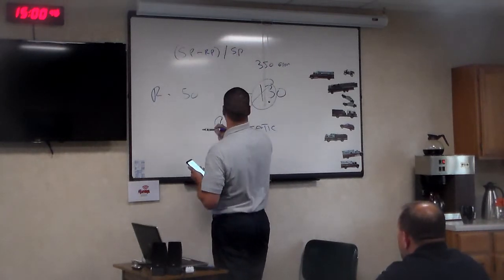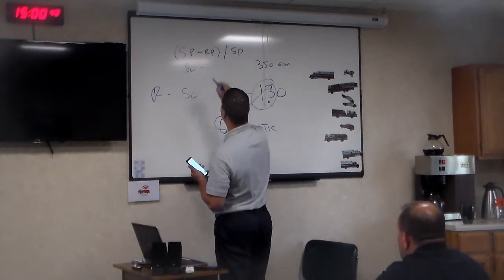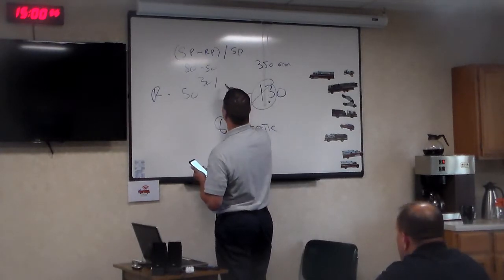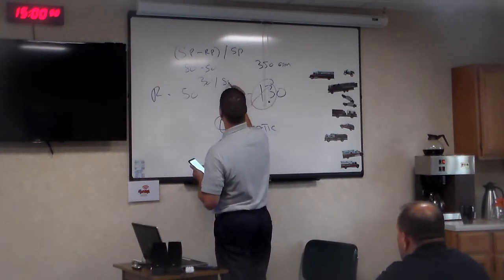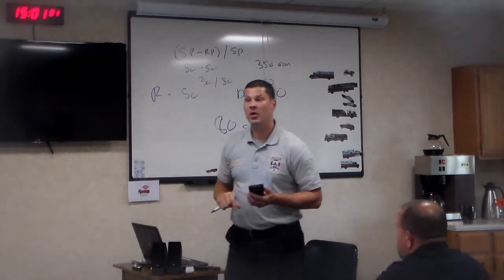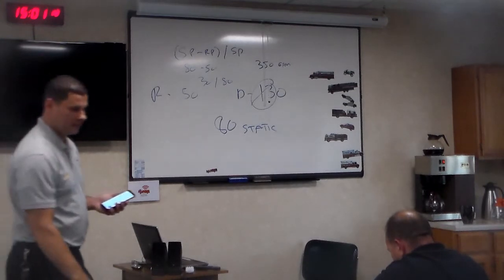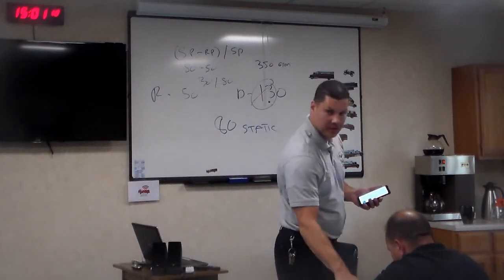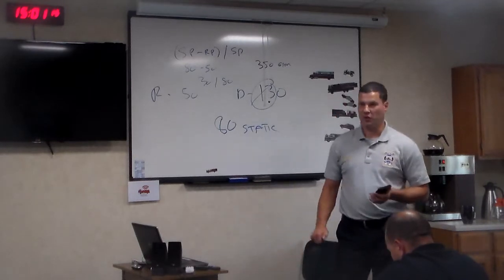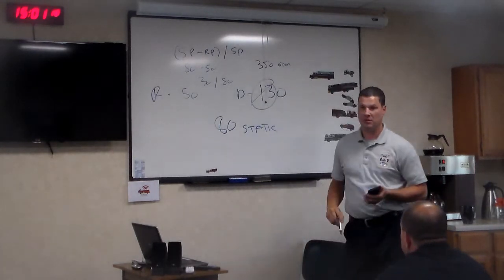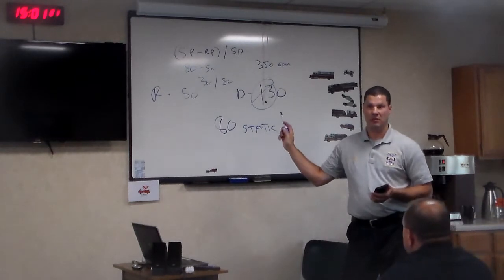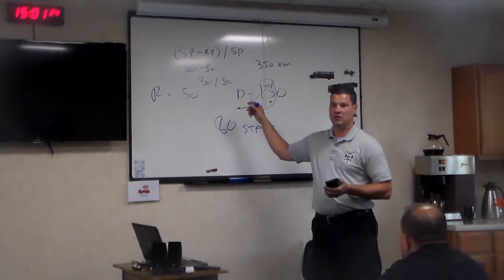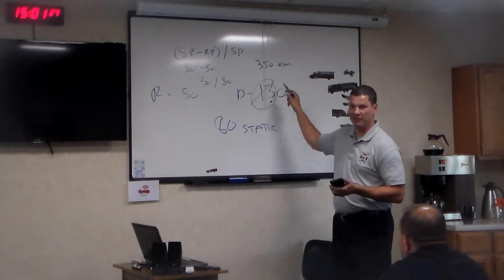Okay. What's the static pressure? 80. What's the residual? 50. What's that? 30. Divided by the static, 80. 30 divided by 80 gets you what? 0.375. What does your chart tell you that means? You can't. And how do we know that? Because we're above 25. Okay? So you cannot flow, at least you can't flow 350. That's what this is telling you. Theoretically, you may be able to flow numbers under that, but we know you can't flow 350.